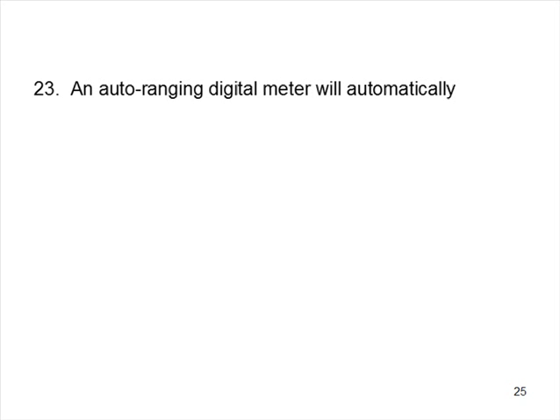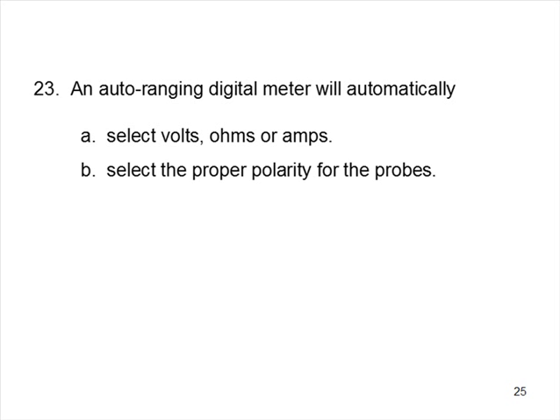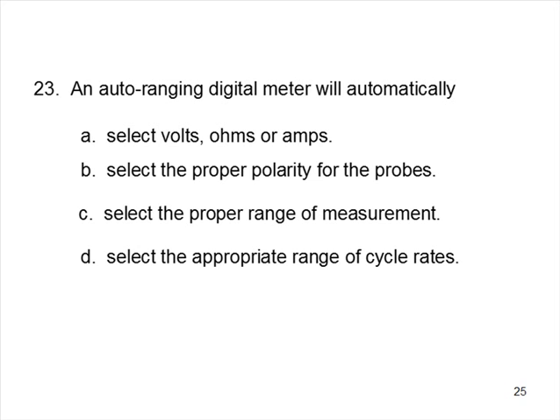23. An auto-ranging digital meter will automatically select volts, amps, or ohms, select the proper polarity for the probes, select the proper range of measurement, select the appropriate range of cycle rates. Well, what is an auto-ranging digital meter going to do? It's going to select the proper range of voltage, amperage, whatever you set it on manually.